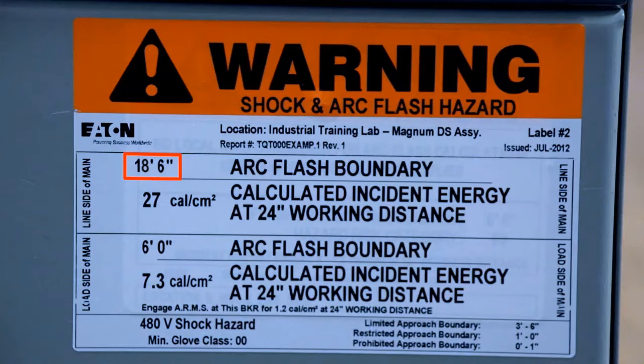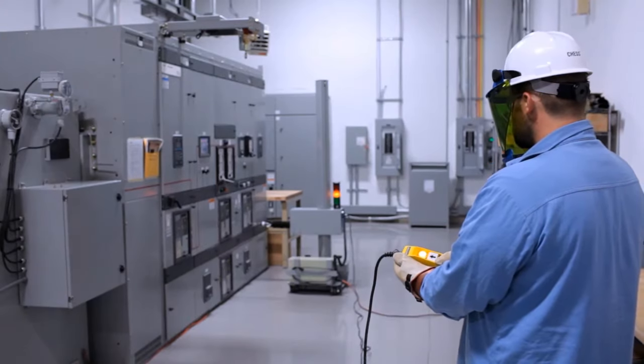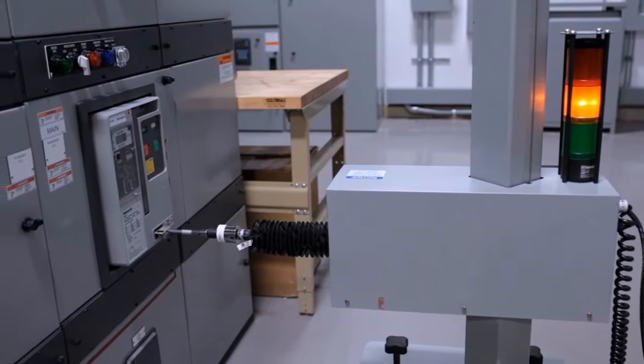The second critical piece of information on this label is distance. This label shows that in order to avoid a 2nd degree burn, a person without arc flash personal protective equipment, or PPE, would have to be 18.5 feet away. The only way to operate on equipment from this distance without PPE is to do so with some type of remote control device or equipment.